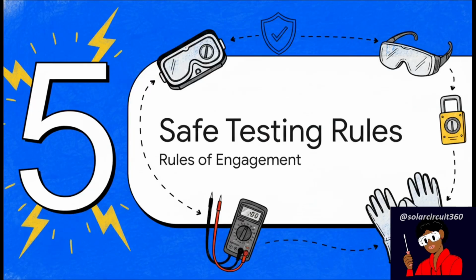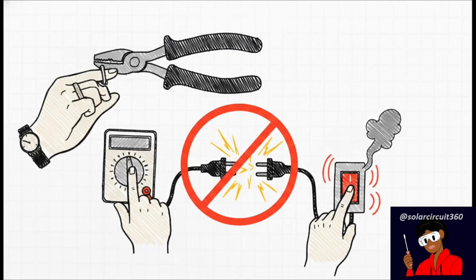Before you grab your tools, let's cover Section 5, Safe Testing Practices, Rules of Engagement. Listen, battery banks deliver incredibly high fault currents, so you really have to respect this energy. For your own protection, always remove metal jewelry before working near terminals, and try to use insulated tools whenever you can. It's also super crucial to double-check your meter settings before taking a measurement. Plugging your probes into the wrong ports can blow up a multimeter in an instant. Never disconnect high current cables while a load is running. And if you ever spot overheating, melted insulation, or hot lugs, power down safely and immediately.